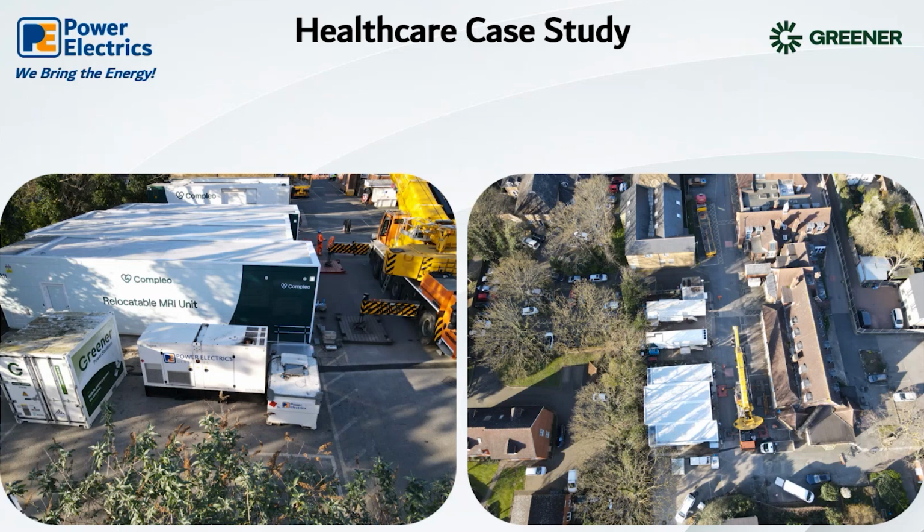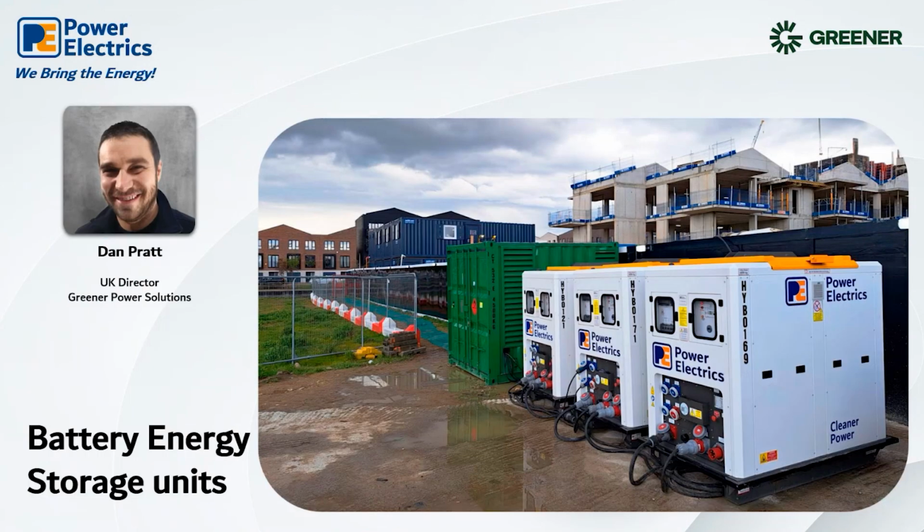For instance, we've seen lots of projects that are requesting huge power supplies from a temporary system, for instance, modular office buildings on construction sites. But really, if you think about how the power is going to be used within those offices, the electrical design might be based on each module within that office block requiring a 32 amp single phase power supply. And if there's around 50 modules, the electrical design might suggest that the peak load requirement is around 530 amps per phase. As a result of this, a 300 to 500 kVA temporary power supply might well be requested.